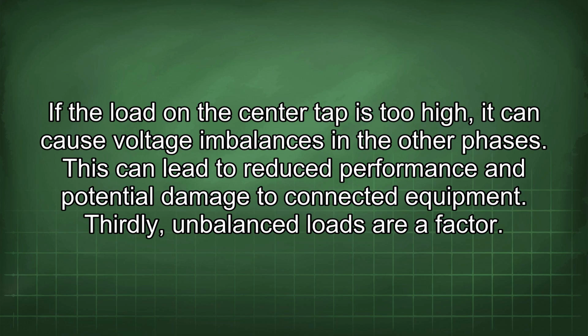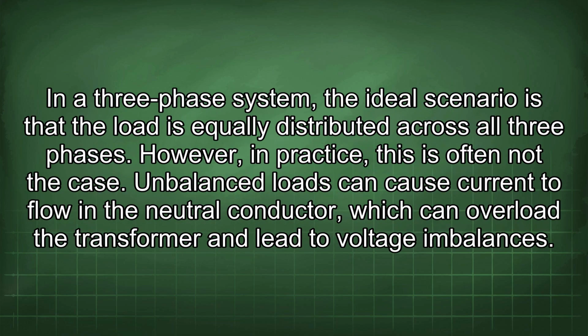Thirdly, unbalanced loads are a factor. In a three-phase system, the ideal scenario is that the load is equally distributed across all three phases. However, in practice, this is often not the case. Unbalanced loads can cause current to flow in the neutral conductor, which can overload the transformer and lead to voltage imbalances.